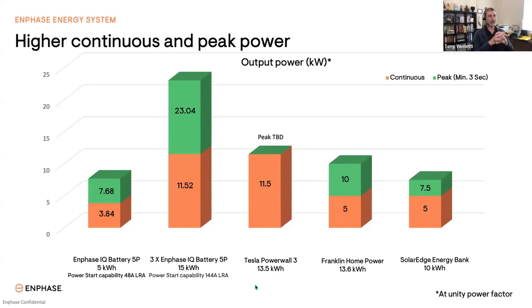So 3 of the IQ Battery 5Ps will have a total storage of 15 kilowatt hours. The total continuous power is 11.5 kilowatts, and the peak power for up to 3 seconds is 23 kilowatts. So again, a ton of power there to be able to start up and run large appliances. And if you note in small print below that, it says power start capability 144 amps LRA. LRA is locked rotor amps.